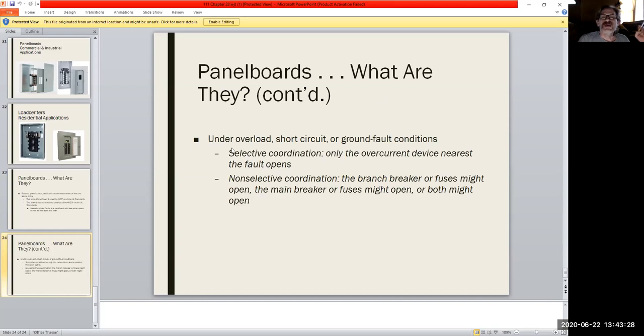But taking a look at it, when you do buy these things, you want to make sure that the rating does meet everything that you've gone through. So if you've gone through all your calculations and whatnot, and this is very standard, you haven't run into anything outside of the ordinary, then when you order up your panel board, you could say, okay, this meets my requirements.